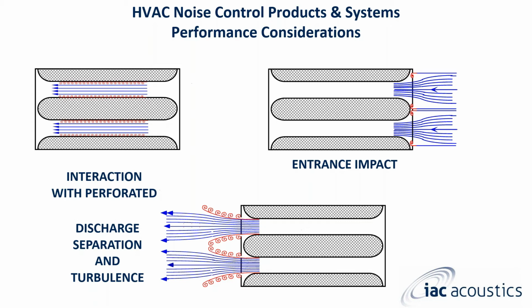So sometimes if it's closer to the actual, say, air handling unit or chiller or cooling tower, you might get some perforated noise. So that is interaction with the perforated. So you might hear a little bit of the whistling noise. You might also, if it's really close, like right underneath the actual air handling unit, have some entrance impact. The nice thing though is that with our bell mouth entrance and exit, the entrance impact is minimal. The same thing with the discharge and separation for the turbulence. It is minimal there as well because the air passages are the same throughout. So literally you're going to have an even flow of air coming in and an even flow of air going out.